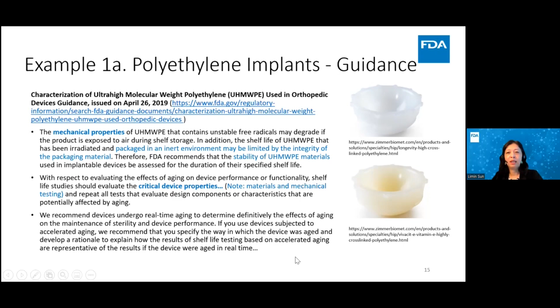While this presentation is focused on the stability of the device, please note that while shelf life has been determined through both packaging integrity and product shelf life testing in premarket review, non-conformance in the integrity of packaging can significantly affect the device stability and lead to device failure, even if the device is within the labeled shelf life. FDA recently issued a safety communication on risks with Exactech joint replacement devices with defective packaging, to remind patients and healthcare providers about the joint replacement devices manufactured by this company and to check their records in the last 2 years. I provided a link here. If you are interested, please check for further information.